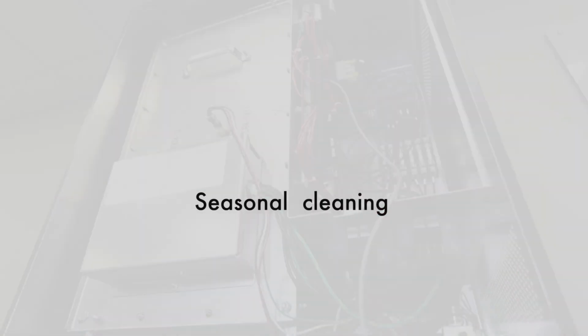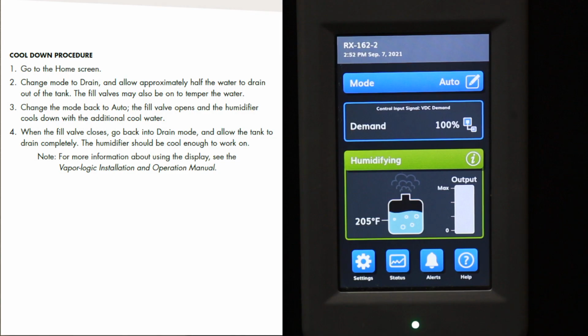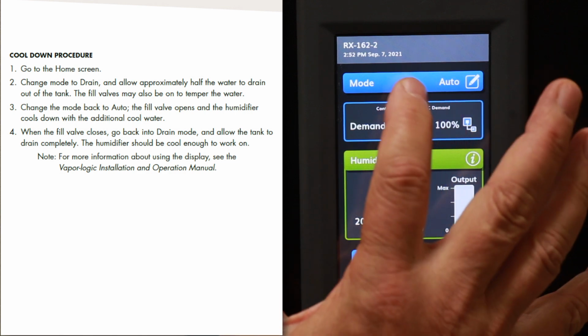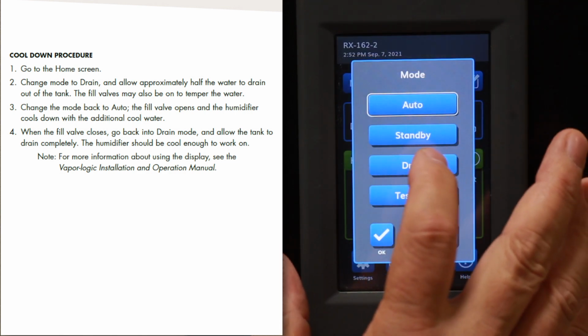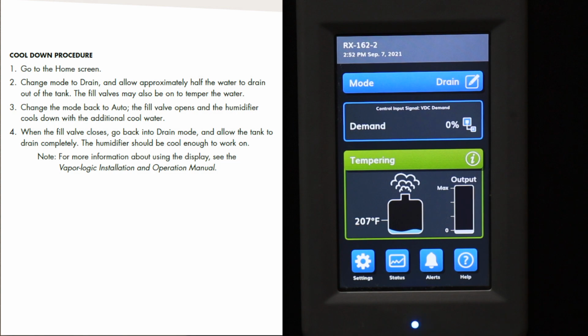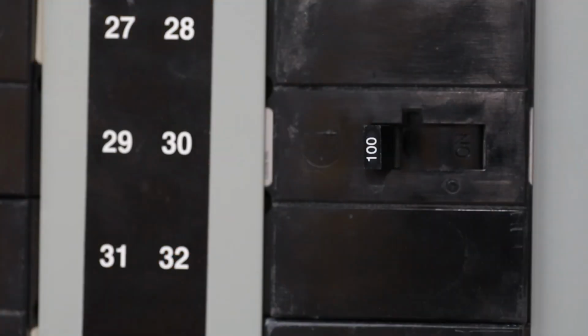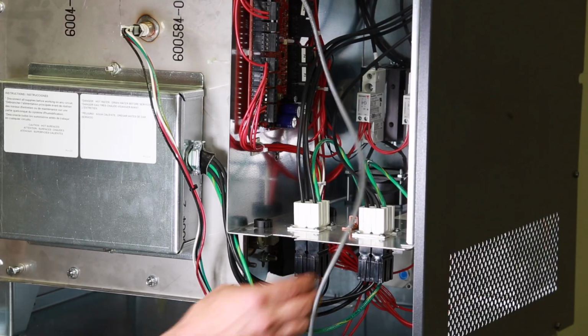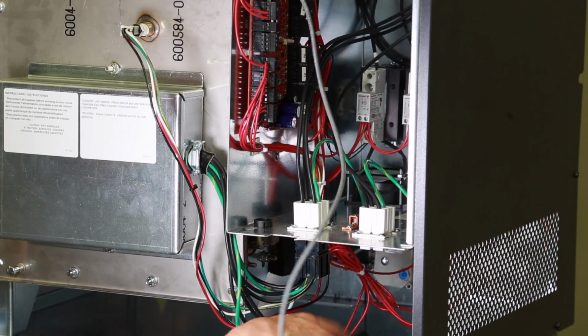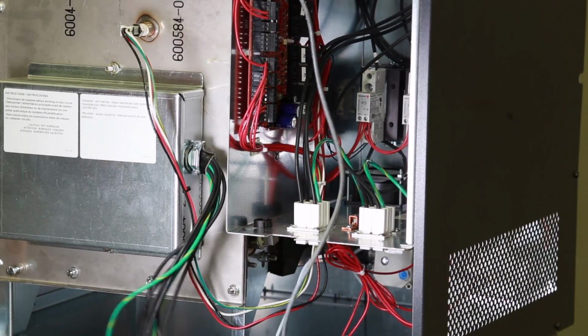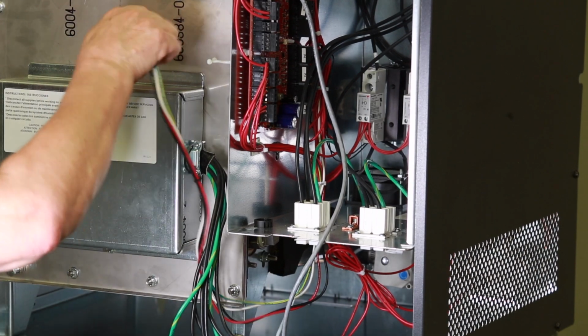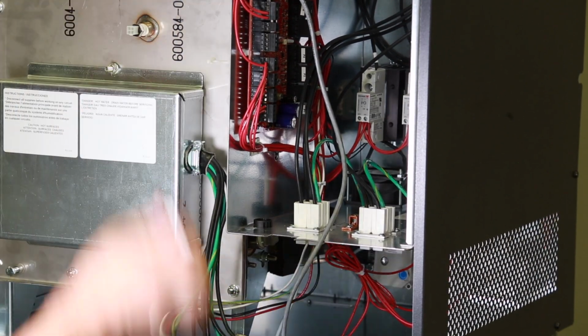Seasonally, or as required depending on water quality, clean the tank and water level probes. If the tank is hot, cool it down first. See Cool Down Humidifier section of the RTS IOM. Allow the tank to drain completely. Shut off the water supply. Shut off the electrical supply. Disconnect the electrical plug between the heaters and the bottom of the electrical panel. There is one connector per stage. Disconnect by pulling on plug housing.